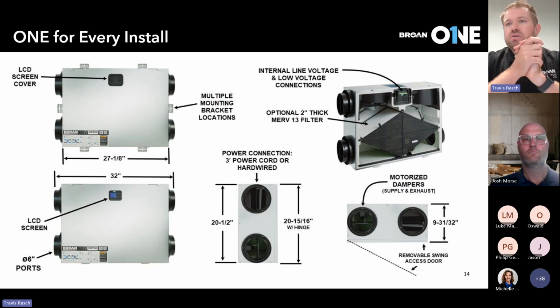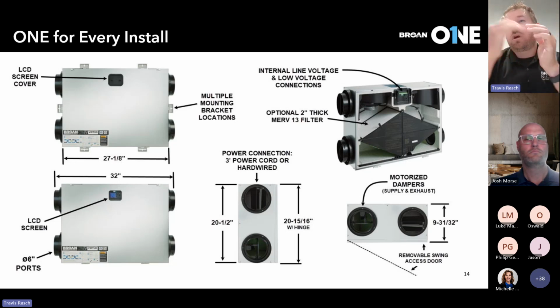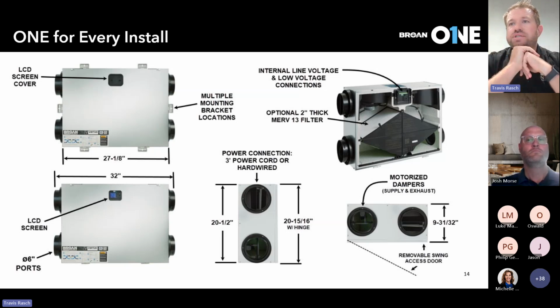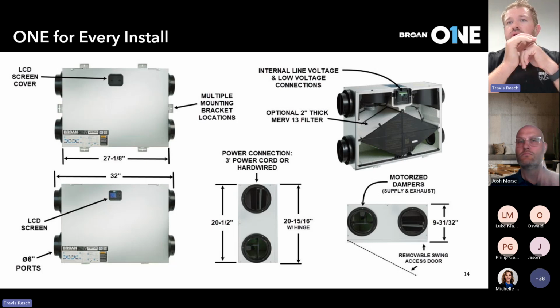Like I said, it swings, and after about 10 degrees of rotation, it can fully come off its hinges. And then from a maintenance access standpoint, you need about 9 inches or so for the recovery core depth from a clearance standpoint. We do have motorized dampers on both sides, a supply and an exhaust motorized damper. So no additional backdraft dampers are required. No additional damper adjustments are required. Those come physically on the product itself, ready to go, and will work accordingly based on the unit operation.